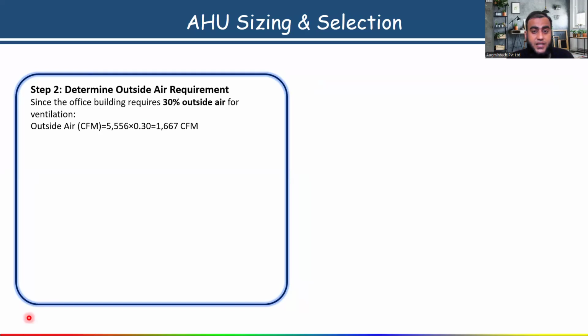5,556. So 30% is 1,000. Yeah, 667 CFM, near about. Okay. So just determine the outside air requirement. The AHU must bring in that much, 1,667 CFM of outside air.